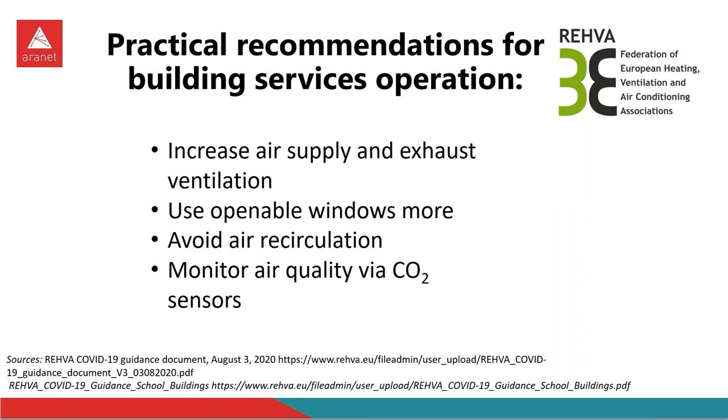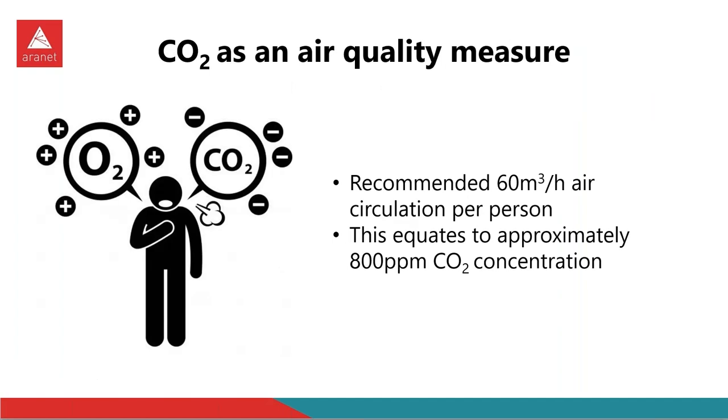And the last thing is to monitor the air quality, monitor how fresh the air is, monitor the quality of ventilation via CO2 sensors. So why CO2 sensors? Well, CO2 is really a nice proxy to use as an air quality measure, because we are all producing CO2. We breathe in oxygen, breathe out CO2. And as everybody knows who has been in a crowded room, the CO2 buildup causes you to feel like there's little air there. So it's a nice indication of whether this air is being exchanged properly.